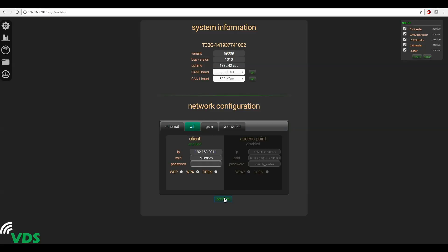You may not get a save confirmation at this point because the settings have already changed and you're no longer connected to this network. What this means is that right now we don't know the IP address that is given to the TC3G because it is dynamically generated at this point. So we have to connect directly to the device through RS-232 in order to ask it what its IP address is.